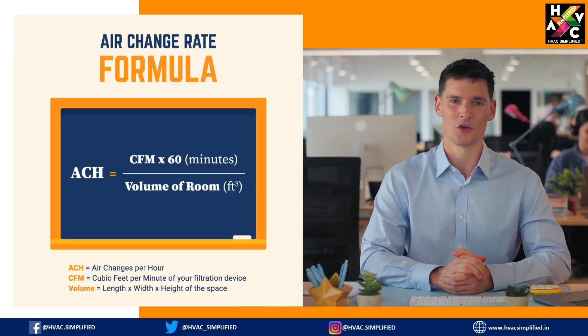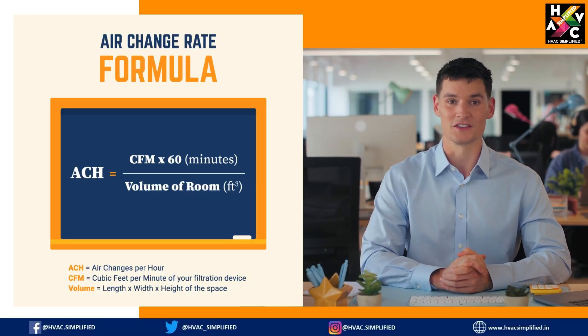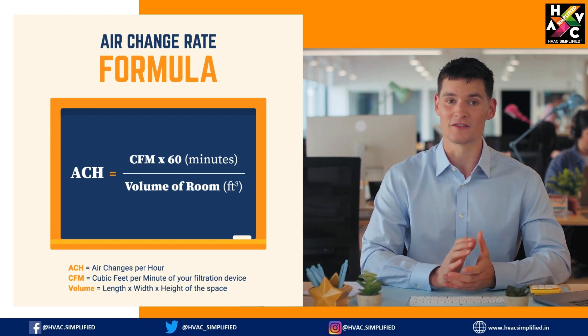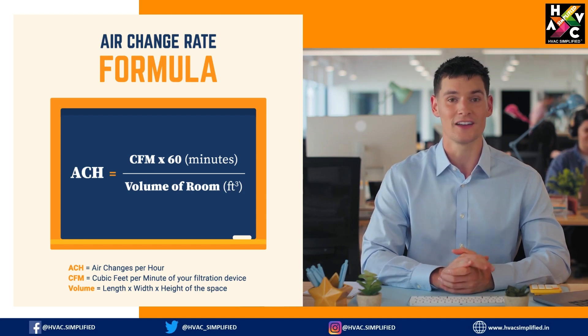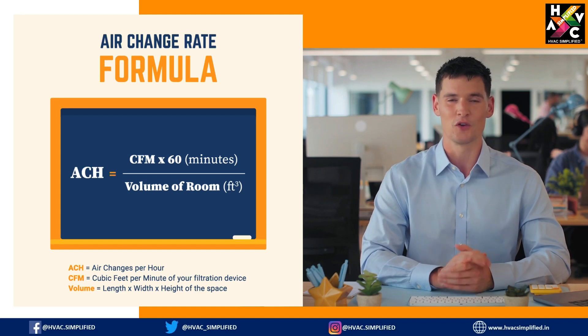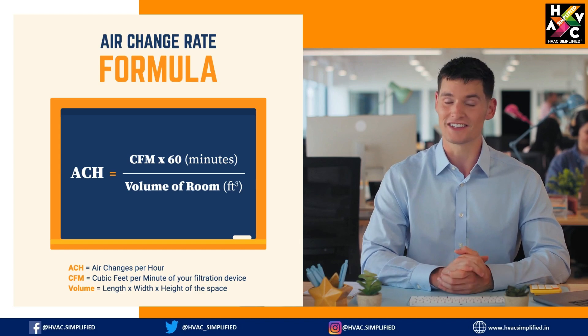Now let's break down the formula for calculating the air changes for a room or space. In this formula, CFM stands for cubic feet per minute, multiplied by 60 minutes, since we are looking for air changes per hour — this represents the flow rate of air. The volume is the total room or space volume that requires ventilation.